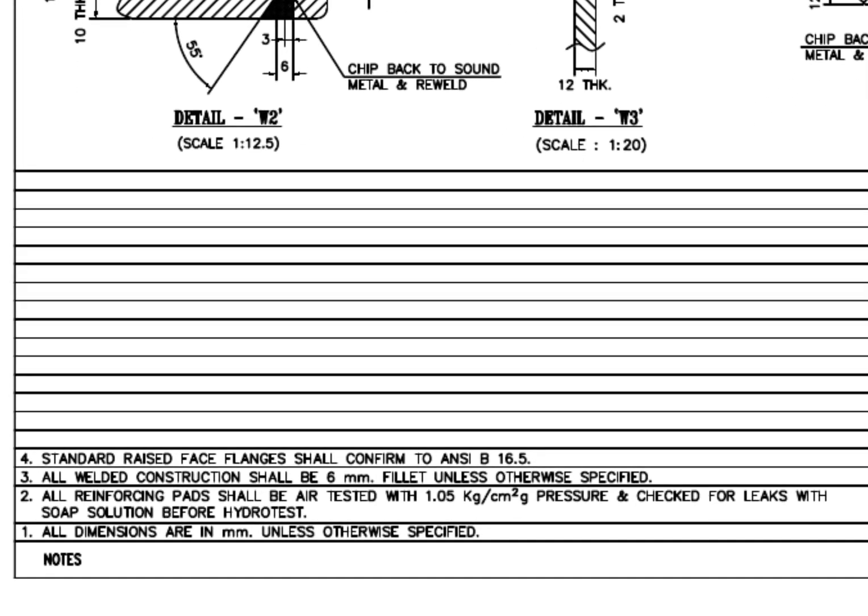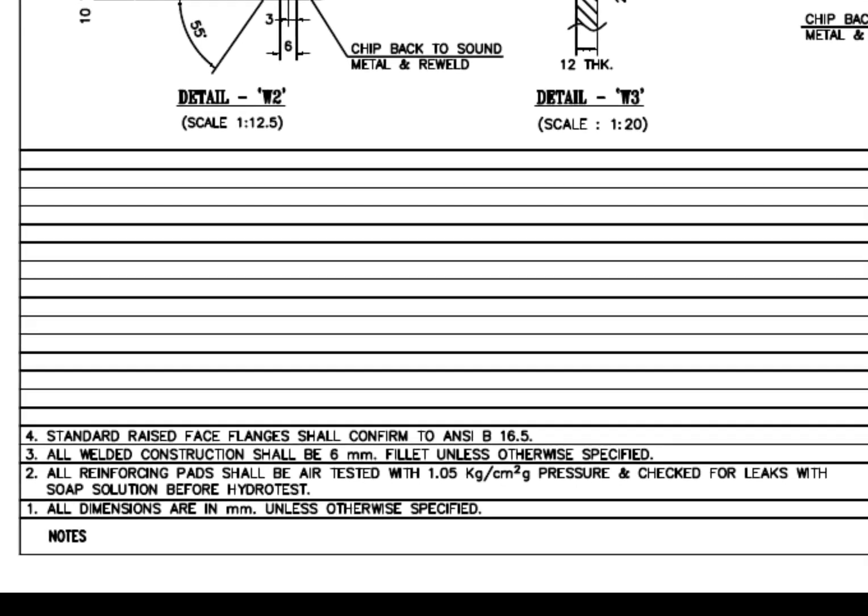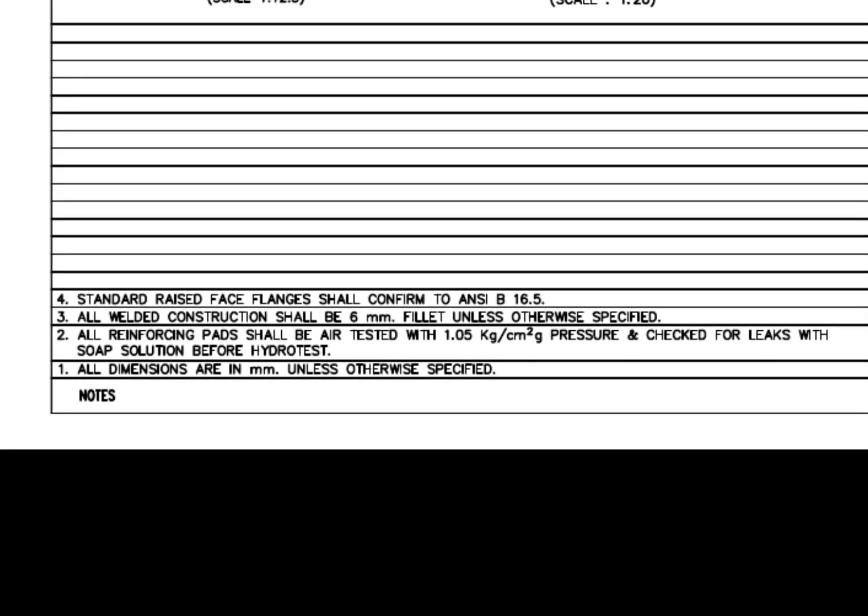Let us check what the notes say. All dimensions are in mm unless otherwise specified. All reinforcing pads shall be air tested with 1.05 kg per centimeter square gauge pressure and checked for leaks with soap solution before hydro test. All welded construction shall be 6 mm unless otherwise specified.